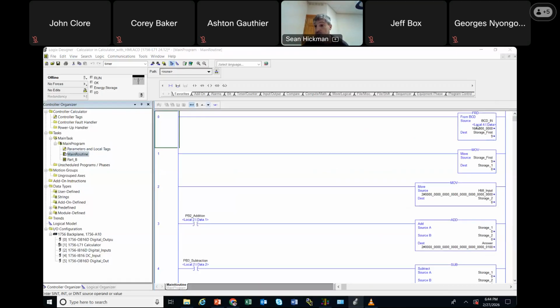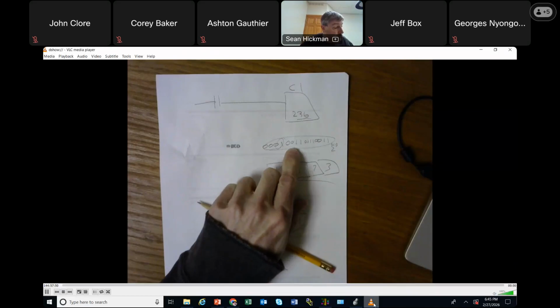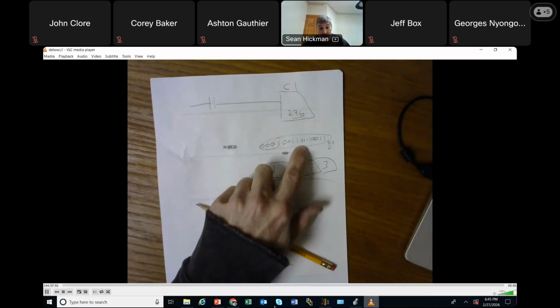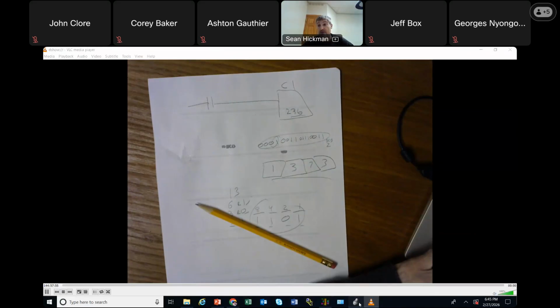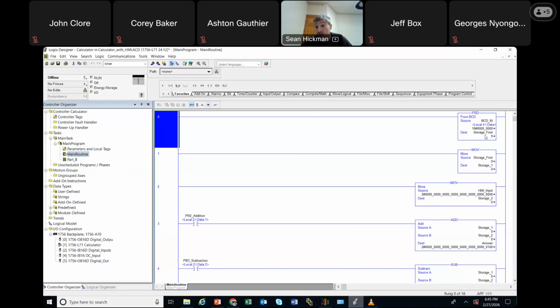We are taking in the entire input module, local 4 data, I guess. That's where you have the wheel wired into 4, or local 5, slot 6, slot 7, whatever slot you're in. That's apparently this one right here. And it's taking the BCD in, the 1001, that BCD in that I showed you right here, this BCD number from whatever our wheel was set, okay? And the purpose of that logic is to then create the number for it. And it would create the number 1373, because that's what it is. It's doing the math for us.